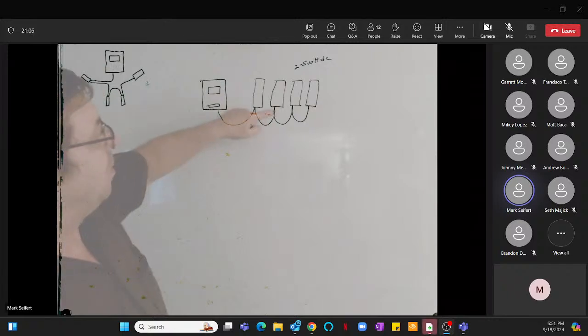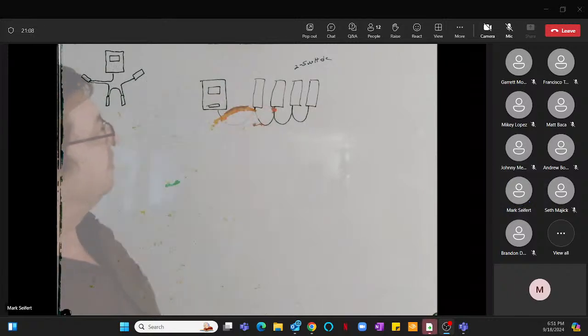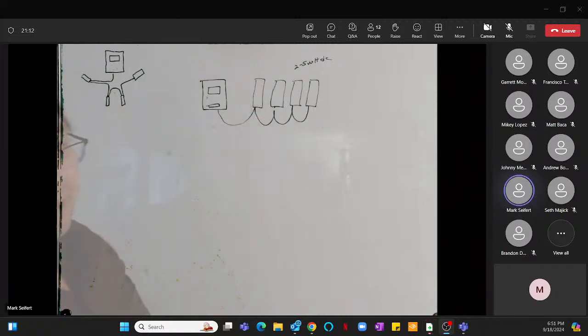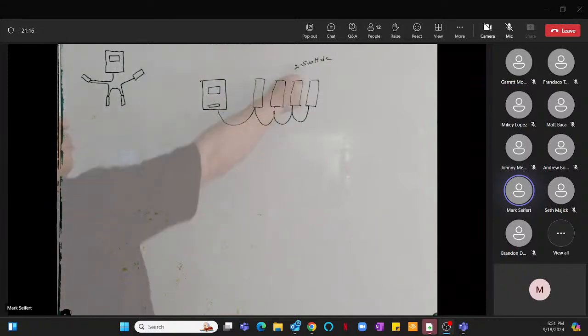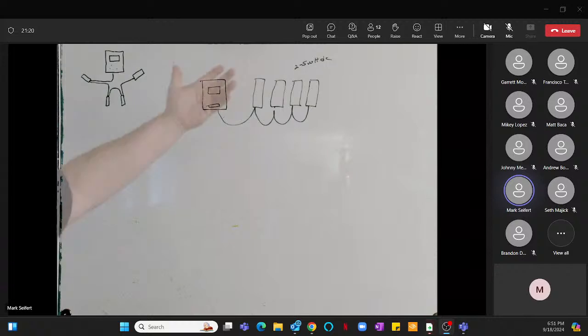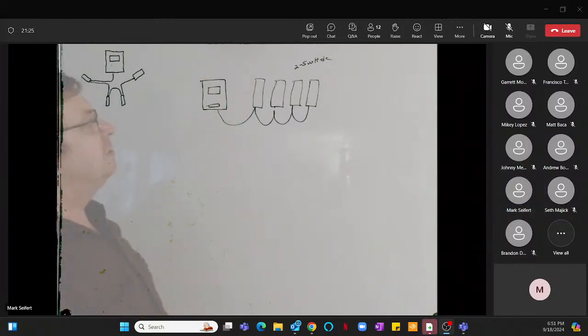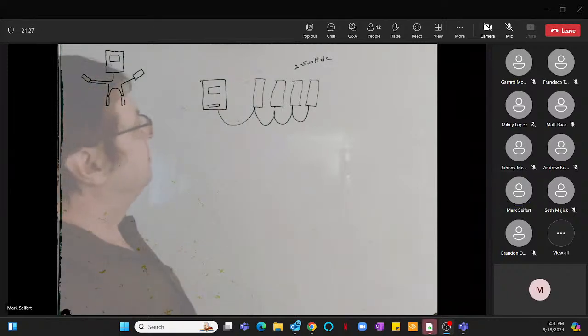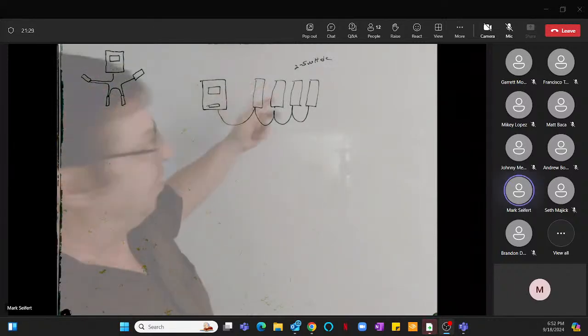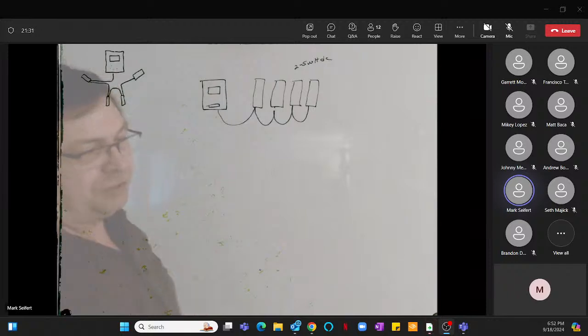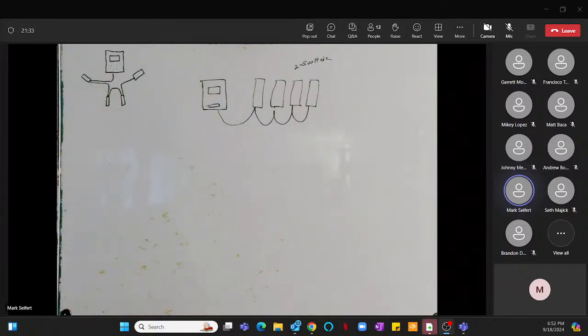You're going to want to always unplug it, take it out of the circuit, and test it without it plugged into the comm loop. Unplugged, this board should put out 2 to 5 volts DC. If it has 2 to 5 volts DC, it doesn't necessarily mean it's good though. I've seen bad boards still put out a DC voltage. It's just the comm chip is messed up or something's messed up in it.